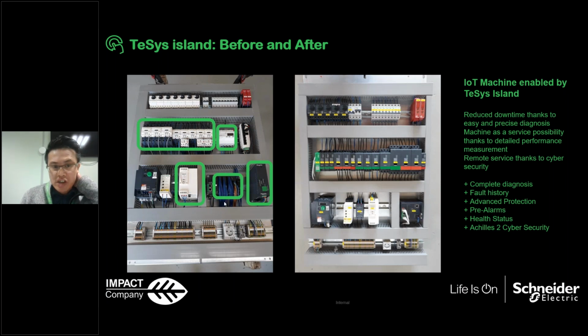and a lot of wiring needs to be considered here. But with the TeSys Island on the right hand side, you will see everything is very tidy, and no power meters are needed because we have already measured the energy for each individual load. Fewer I/O interface modules to the PLC are needed because we have the AI modules and the digital modules, so you can have all the data into the system and then to the PLC.